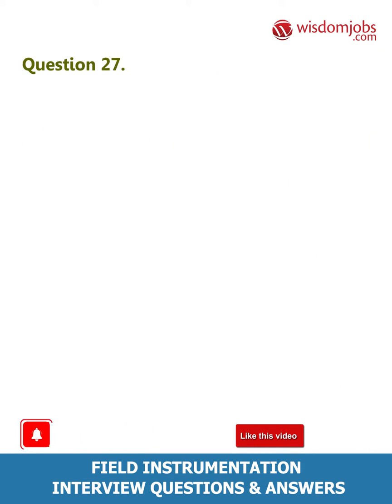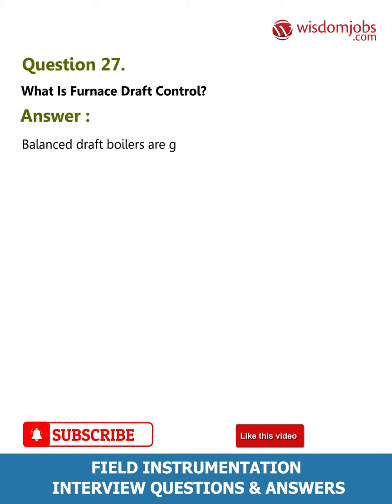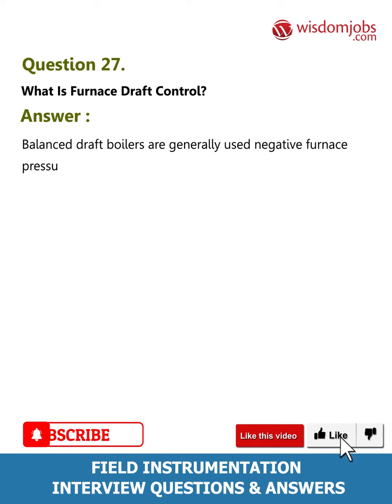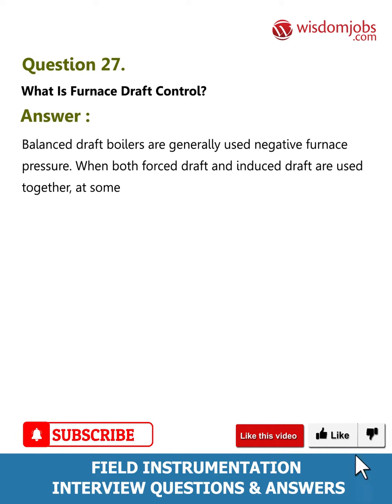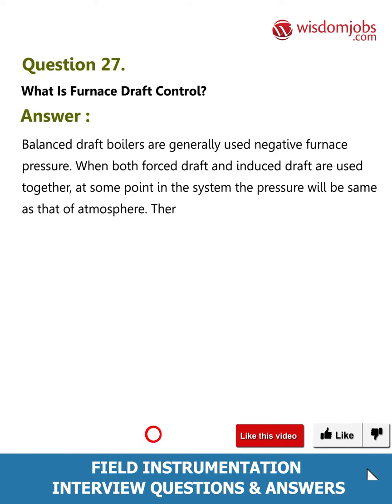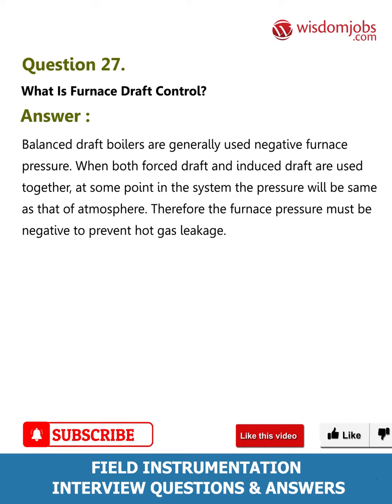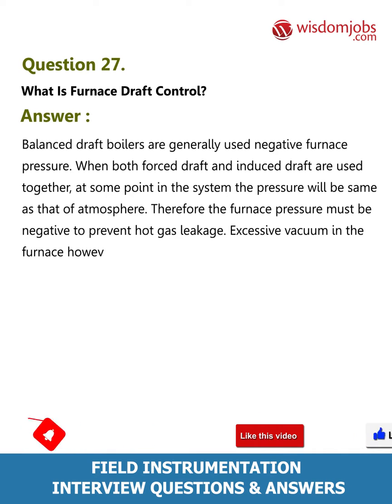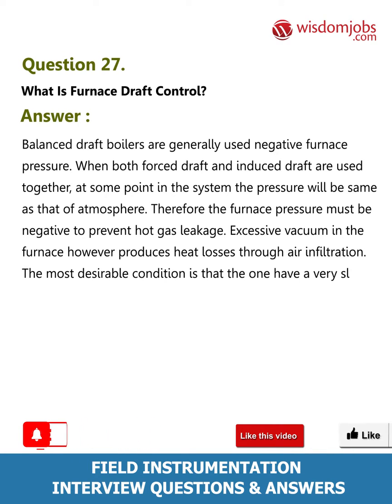Question 27: What is furnace draft control? Answer: Balanced draft boilers generally use negative furnace pressure when both forced draft and induced draft are used together. At some point in the system the pressure will be the same as that of the atmosphere. The furnace pressure must be negative to prevent hot gas leakage, but excessive vacuum produces heat losses through air infiltration. The most desirable condition is to have a very slight negative pressure at the top of the furnace.